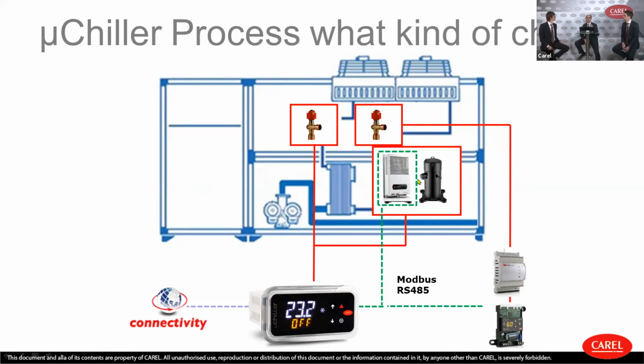The variable speed compressor was always seen as an energy-saving technology, or for process chillers as a way to control supply temperature. But we never thought this actually increases reliability, because with envelope control you limit the speed of the compressor depending on conditions. So if your condenser is dirty, instead of tripping a high pressure alarm, you just limit the compressor speed and try to provide some business continuity.